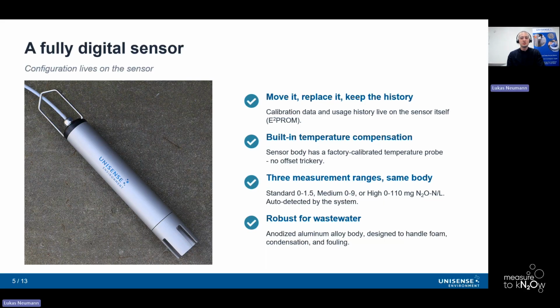So then we have the fully digital sensor. This is really the biggest architectural change compared to the previous generation. Previously, the calibration data lived in the controller. So when you moved a sensor to a different area, oftentimes you would have to recalibrate. Now the sensor is self-aware and remembers itself. So you can move it, replace it, you keep the history. You can swap the head, move the body to a new tank. You can even move it to a different plant, and the calibration data and the history all come with it.